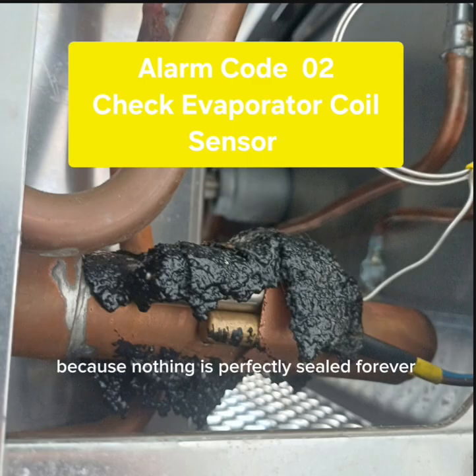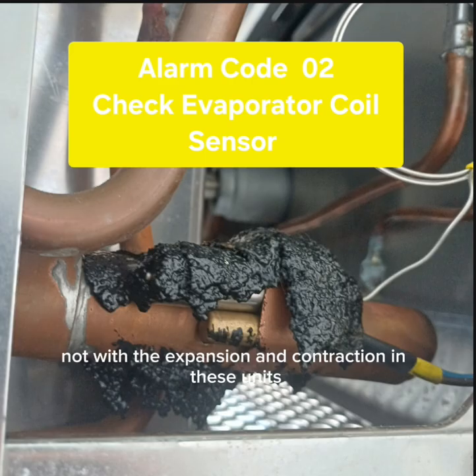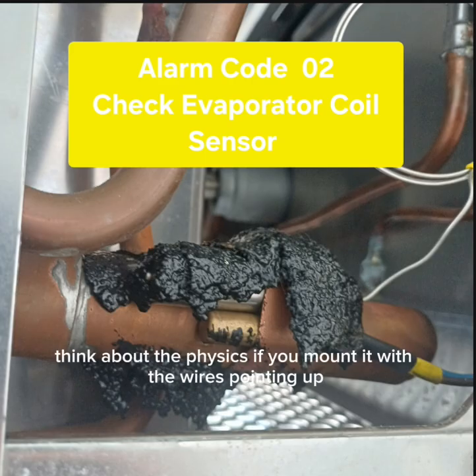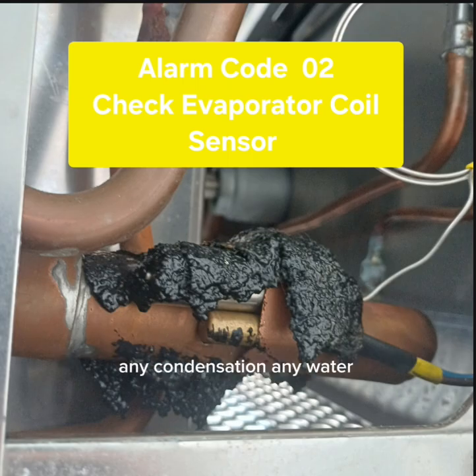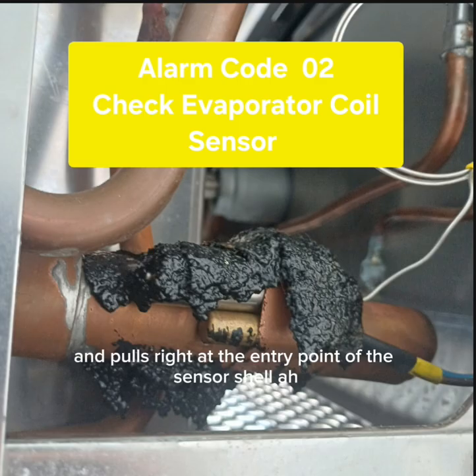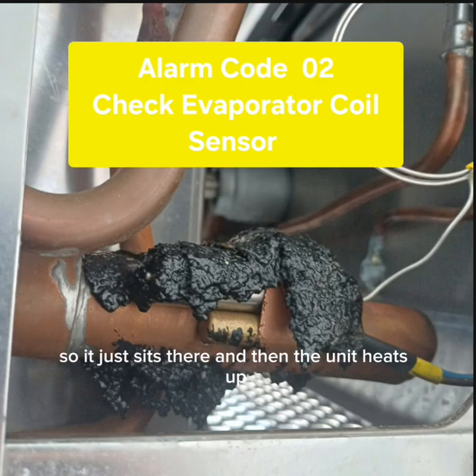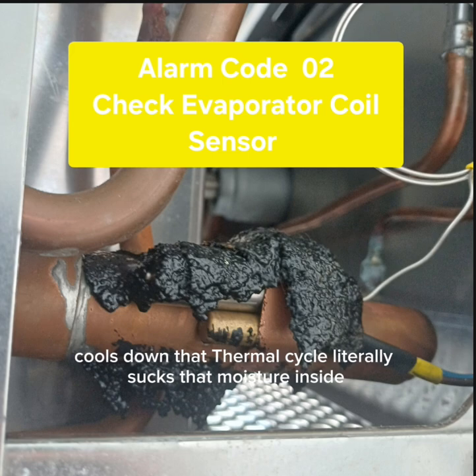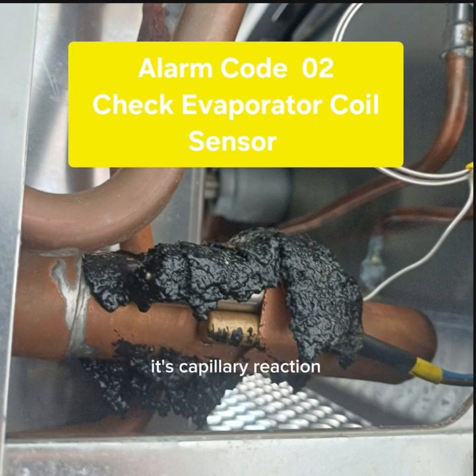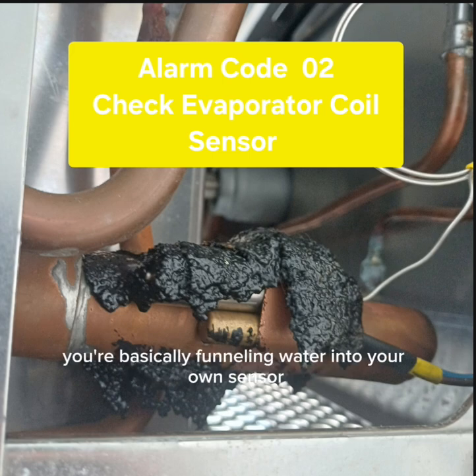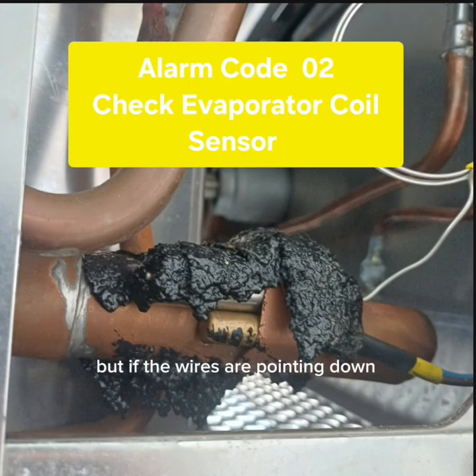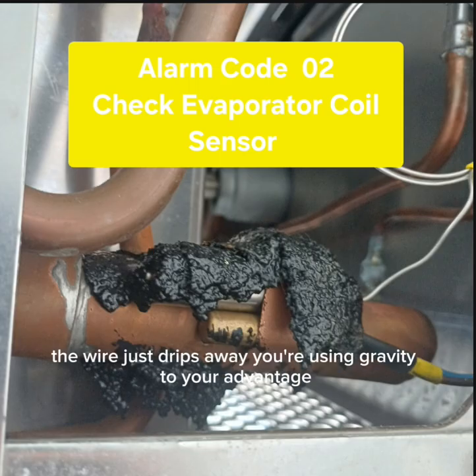Because nothing is perfectly sealed forever. Not with the expansion and contraction in these units. Think about the physics. If you mount it with the wires pointing up, any condensation, any water, runs down the wire and pools right at the entry point of the sensor shell. Ah, so it just sits there. And then the unit heats up, cools down. That thermal cycle literally sucks that moisture inside. It's capillary action. You're basically funneling water into your own sensor. But if the wires are pointing down, the water just drips away.